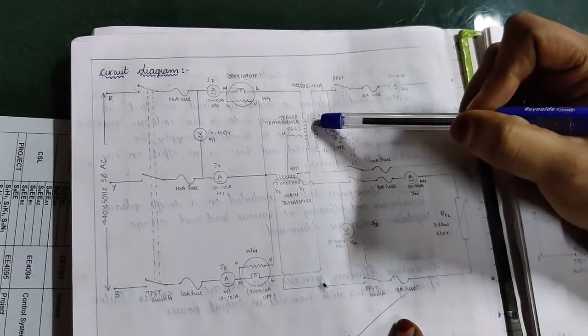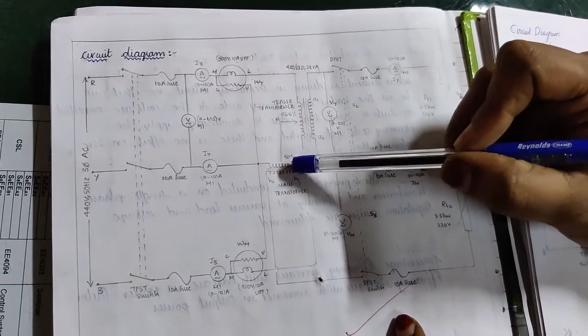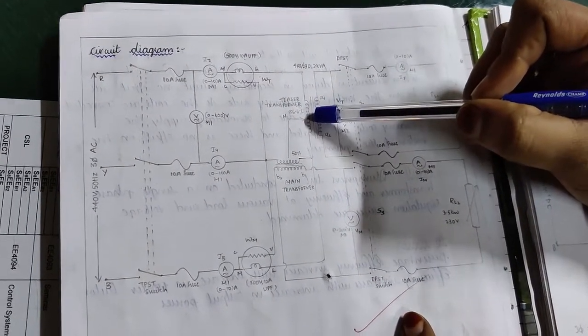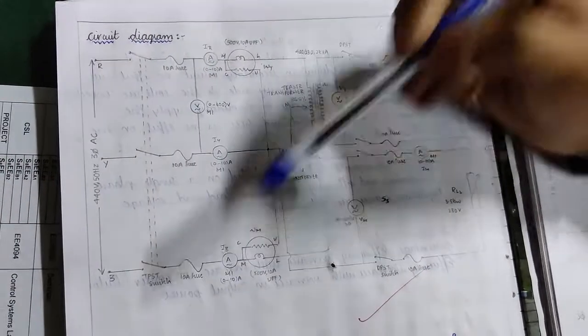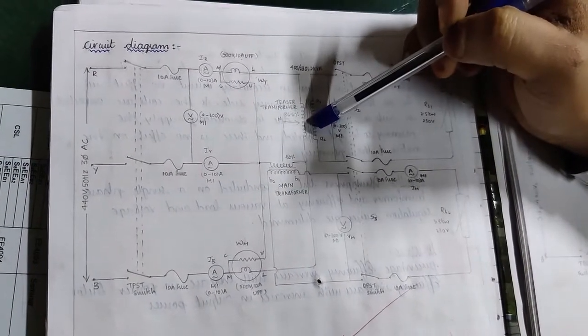One is termed as main transformer and the other one is teaser transformer. And from the 50% tapping of the main transformer, there is a connection to the 86.6% of the teaser transformer. The two ends of the main transformer primary is connected to Y phase and B phase, and the center tap is connected to the 86.6% of the teaser transformer. And for both the transformers, the secondary is connected across the loads.